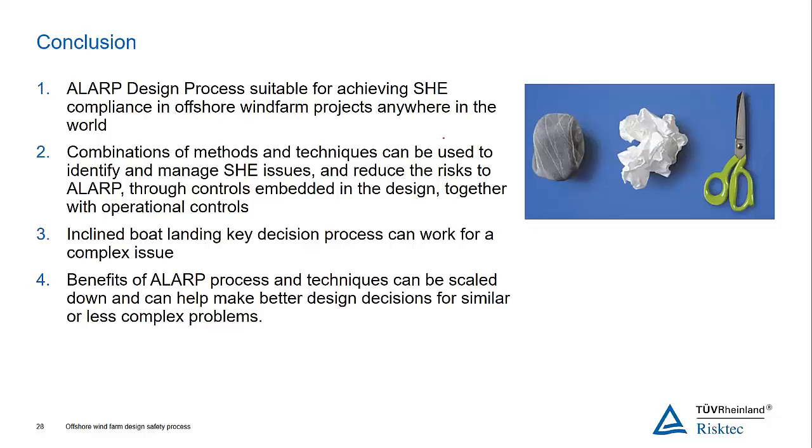But that environmental impact is generally something you would consider in this process. So in your risk assessment, where you looked at consequences, you would have safety and health consequence criteria, and alongside that you have environmental consequence criteria from high through to low. By applying the matrix in the same way, you can apply the consequences and the likelihood of that incident, and put that environmental risk on in terms of high risk, medium risk, low risk, and how acceptable it is. So that would be my answer there.